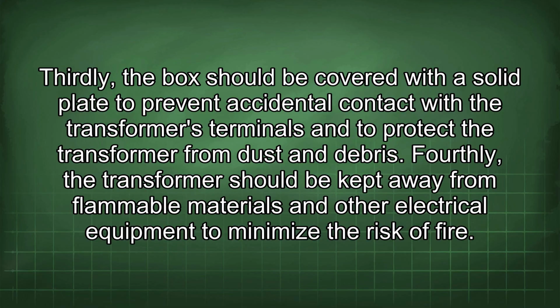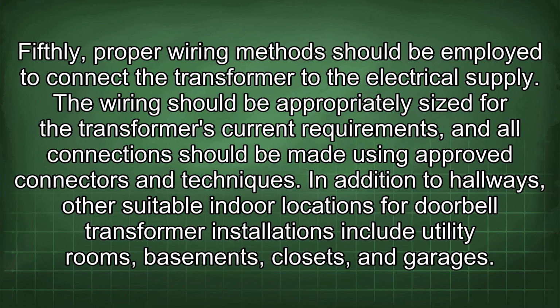Fourthly, the transformer should be kept away from flammable materials and other electrical equipment to minimize the risk of fire. Fifthly, proper wiring methods should be employed to connect the transformer to the electrical supply. The wiring should be appropriately sized for the transformer's current requirements, and all connections should be made using approved connectors and techniques.